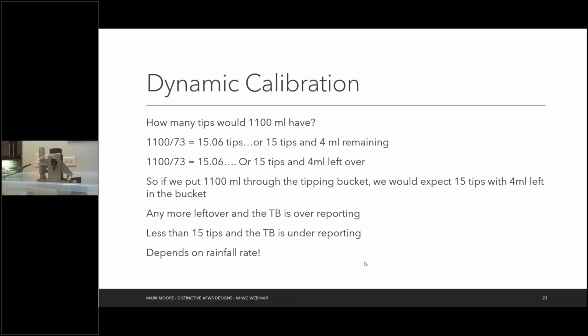Any more left over and that tipping bucket is over-reporting. Less than 15 tips and the tipping bucket is under-reporting. If we put that amount of water through the tipping bucket and we're expecting it to tip 15 times, but it only tipped 14 times, well, guess what? We're not tipping as much as we should be. And then we can use that information to adjust those set screws until we get closer to what we expect to get.